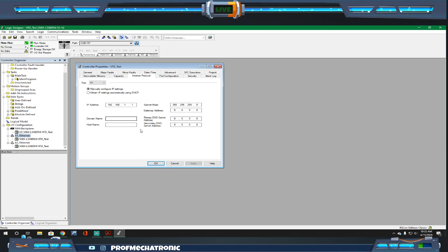So we look here, we've got a port A. We definitely want this to be manually configured. We look at the current setup: the IP address is 192.168.1.1, and our subnet mask is 255.255.255.0. That looks all good to me, that's the setting we want to use for this particular case. So we're going to hit OK on that. Now we know our PLC is on the same network as our drive itself.